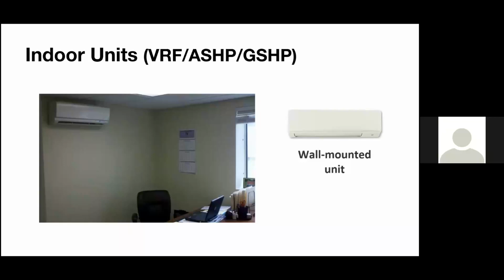So starting off, we're starting off with a wall-mounted unit. Just to give you a little background, these are the most popular units worldwide. Over in Japan for HVAC, they're probably using about 95% heat pumps over there. That's where VRF was basically first invented. So all of those heat pump systems have a wall-mounted unit basically on every single one. And then if you look at Europe, Southern Europe, maybe we're at 75% heat pumps for these wall-mounted units. So they're really everywhere. It's the popular choice. And America is starting to gain a little more traction towards actually using these guys.